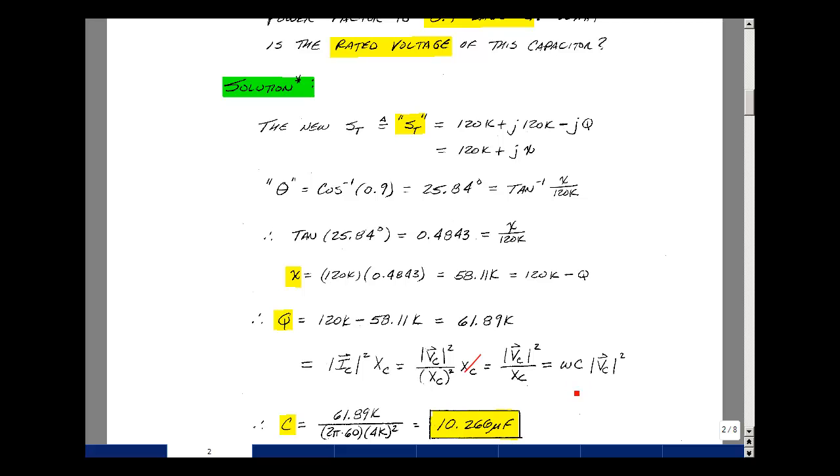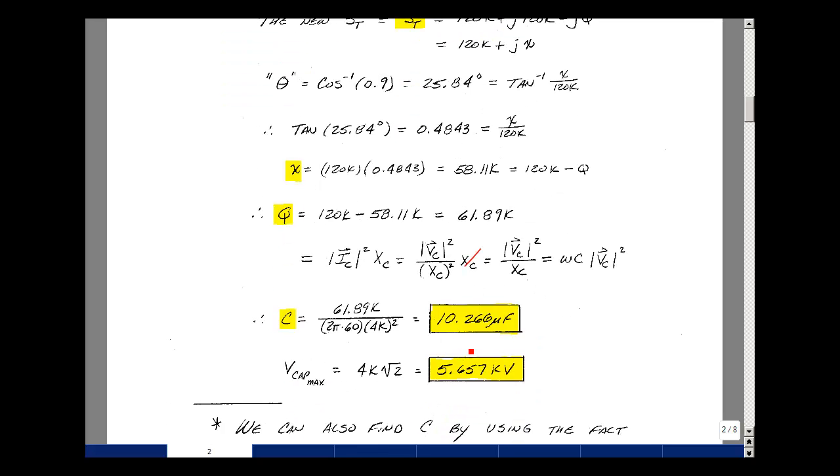So now I can solve for the capacitor value. So we take the value of Q, which is 61.89k, and divide that by 2 pi F, which is at 60 hertz, and then the magnitude of my voltage, which is a 4,000 volt RMS signal. I get a value of 10.266 microfarads.